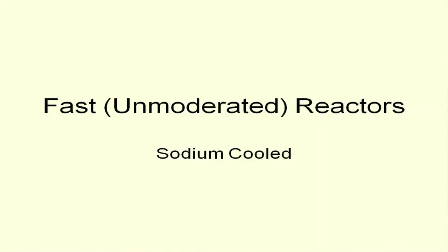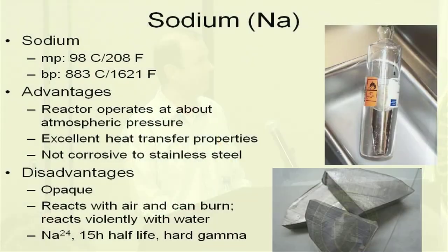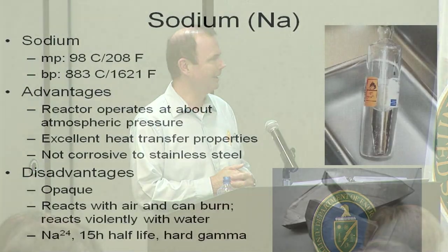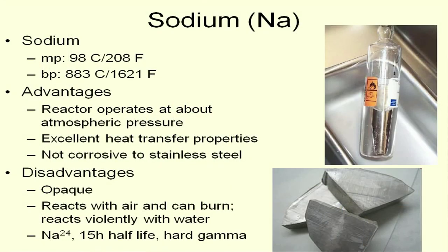Now I want to move on and talk about fast reactors, sodium-cooled. First, a little bit about sodium. Melting point, just about the boiling point of water. Boiling point is up 1600 F, which is quite high. The reactor itself operates about at atmospheric pressure. It has excellent heat transfer properties. It's not particularly corrosive to stainless steel, which is sort of the good news. The bad news, you can see over on the right, there's liquid and then solid down at the bottom. It's opaque. Being sodium, it reacts with air and can burn. If it gets near water, it reacts violently, makes sodium hydroxide and our friend hydrogen again, which of course likes to explode.